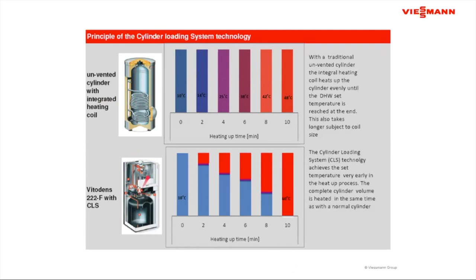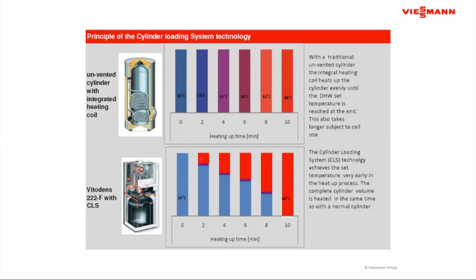With this system, when I fire this up to make hot water, it dumps water into the top of the tank and it stays stratified. So on minute zero, I may have no hot water in the tank at all. After 2 minutes, I have about 6 gallons of hot water in that tank ready for use. So I can turn this on and, like a combi, immediately, if I don't exceed how much hot water it can produce, I could keep that tank almost all cold with a thin layer of hot water and be able to provide hot water out to the building. And then as the time goes by, it starts to load that tank up.